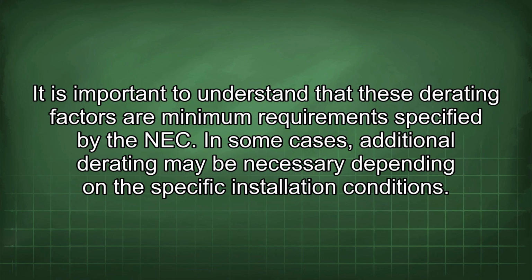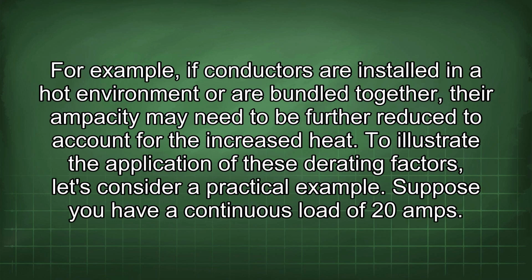It is important to understand that these derating factors are minimum requirements specified by the NEC. In some cases, additional derating may be necessary depending on the specific installation conditions. For example, if conductors are installed in a hot environment or are bundled together, their ampacity may need to be further reduced to account for the increased heat.